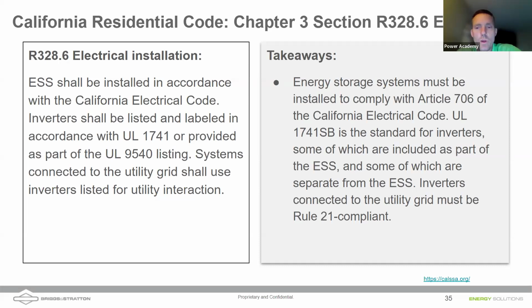When we have multiple sources of electricity all feeding onto a common electrical grid, there's potential for distortion and challenges with systems being out of phase with each other. So this 1741 SA/SB ruling is basically to maintain a standard level for the power coming out of an energy storage system interacting with the grid. A lot of the newer inverters on the market already have these latest UL 1741 standards, so be careful what you install — you don't want to install something without the appropriate certifications, because it could get expensive for you, and as an installer you're responsible for your installation.